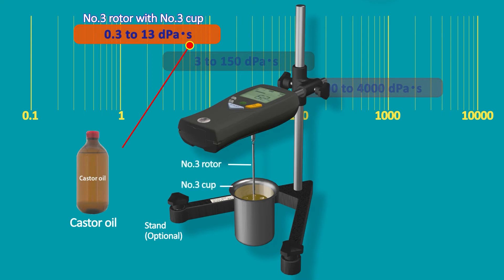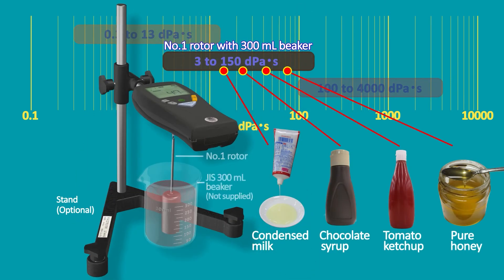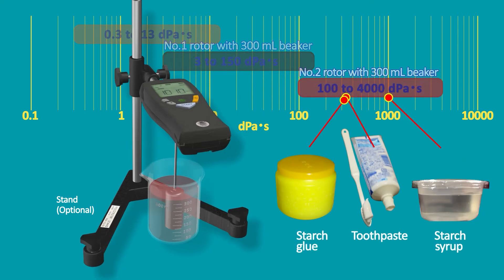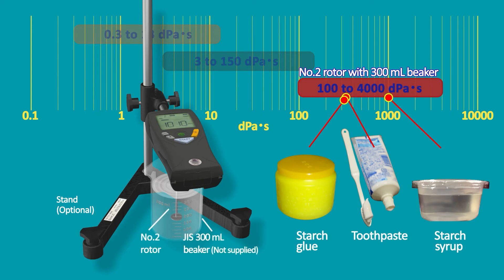The number three rotor with the number three cup covers 0.3 to 13 decipascal fluids. The number one rotor with the JIS 300ml beaker covers 3 to 150 decipascal fluids. The number two rotor with the JIS 300ml beaker covers 100 to 4000 decipascal fluids.